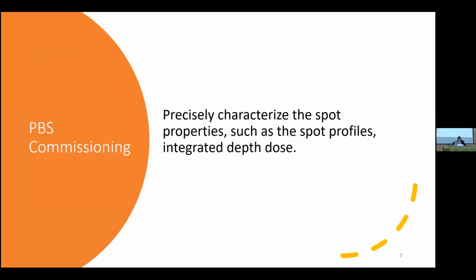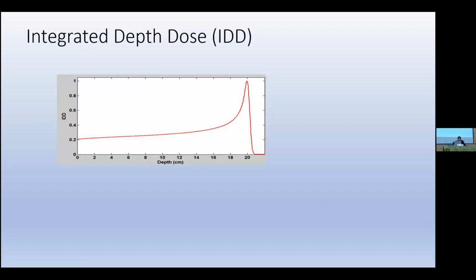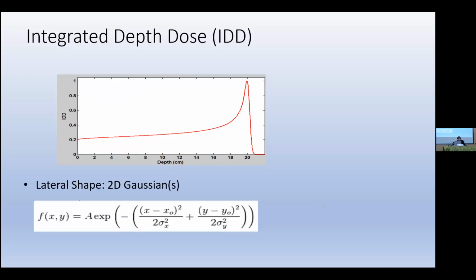Okay. So the first thing when you're doing these commissioning, you need to precisely characterize the spot properties, such as the profile. The main things are the profile and the depth dose. Here we call it the integrated depth dose for now. So here's the integrated depth dose. What this is a measurement of saying how much radiation is being delivered for a particular energy through the depth of, here in this case, a water phantom.